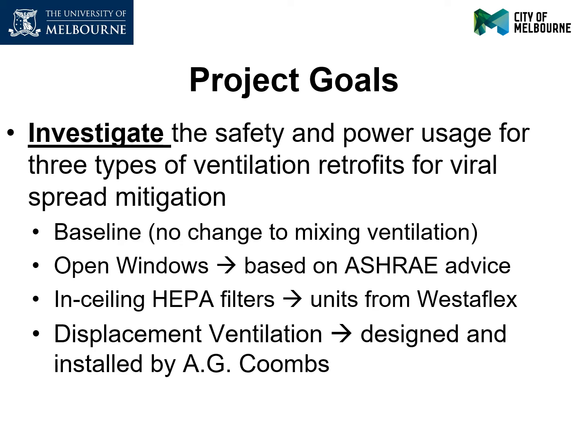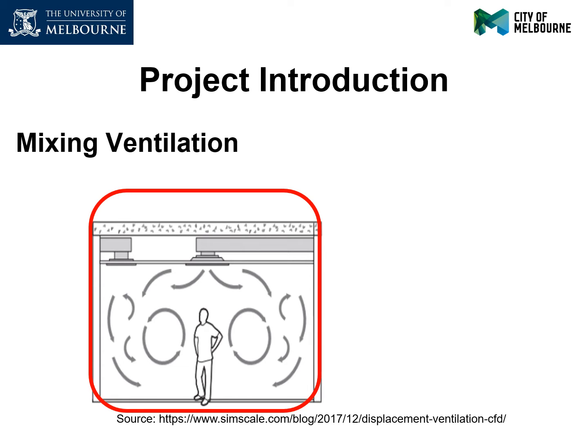Three retrofit options were explored. In addition to this, we also examined the standard operation baseline case. These retrofit options were open windows, displacement ventilation, and in-ceiling HEPA filters. The baseline standard operation option was the business as usual case where no changes to mixing ventilation occurred. We studied this primarily to help us determine the relationship between building power usage and outside air temperature in the archival data.